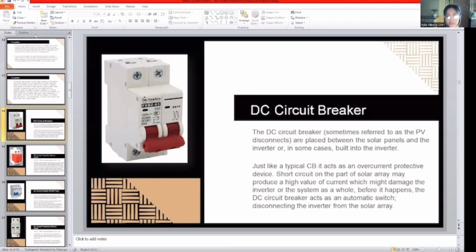So yung third part po is DC circuit breaker. The DC circuit breaker, sometimes referred to as a PV disconnect, is placed between the solar panels and the inverter, or in some cases built into the inverter. Just like a typical CB, it acts as an overcurrent protective device. A short circuit on the part of the solar array may produce a high value of current which might damage the inverter or the system as a whole. Before it happens, the DC circuit breaker acts as an automatic switch, disconnecting the inverter from the solar array.